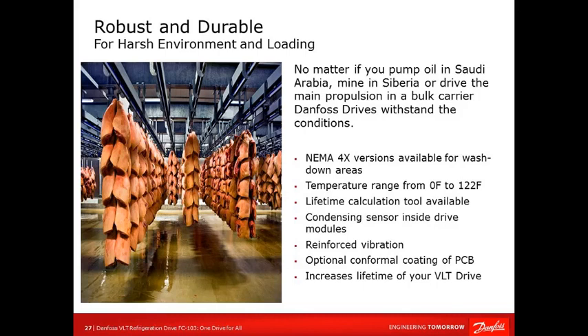Here, really, if you're thinking from a temperature standpoint, we have a lot of other players in the market where they actually have to derate if the drive ambient temperature gets to a certain height, like over 120 degrees, then you have to start to derate. What that means is they have to size a drive larger than needed. Part of that is just the drive has to be able to cool itself off. Where Danfoss, we can go from 0F to 122F. And the advantage then is maybe if you're in a hot engine room, for example, you're not going to have to add air conditioning or something for the temperature. Or if you're in another environment where obviously it's getting colder, maybe you don't need to use heaters, for example.